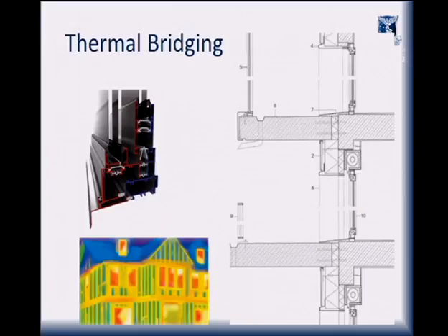And the thermal images capture that. So the framing here, windows losing heat, framing not so bad, but still a bit of heat transfer, insulated wall, pretty good.